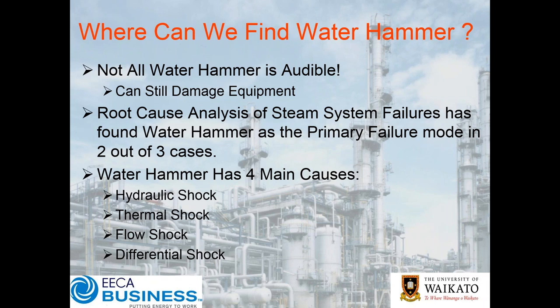Another warning: you might think you don't have a problem because you can't hear it. Not all water hammer is audible. In a lot of plants, everything's lagged and insulated and it might not be immediately obvious — but damage can still be occurring, especially to sensitive equipment. The root cause analysis of steam system failures has found water hammer is the primary failure mode in two out of three cases. Two out of three failures in a steam system with a full RCA analysis is generally found to have water hammer as by far the leading cause.